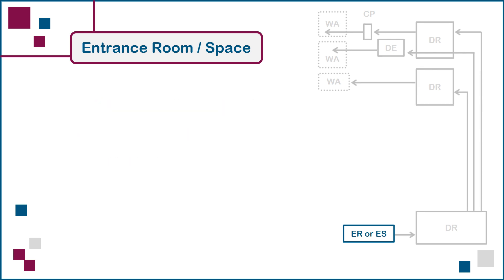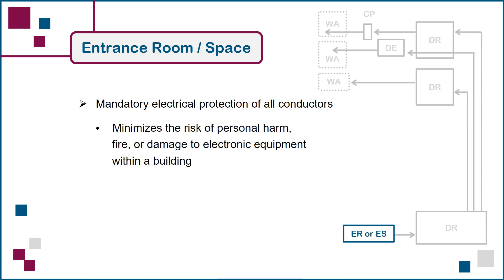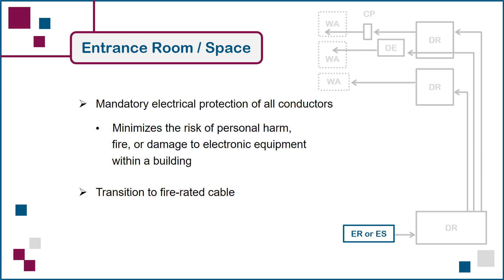The entrance room or entrance space also includes the mandatory electrical protection of all conductors, necessary to prevent the entry into the building of any hazardous voltages and currents through the incoming cables. This minimizes the risk of personal harm, fire or damage to electronic equipment within a building, from such things as a lightning strike near the path of an outdoor telecommunications cable containing conductive elements, such as the conductors in a copper cable or metal armoring in an optical fiber cable. And if the incoming cable is not fire rated for indoor use, a transition to fire rated cable can be made in the entrance room or entrance space using splices or connectors.